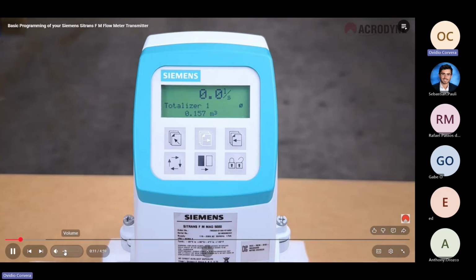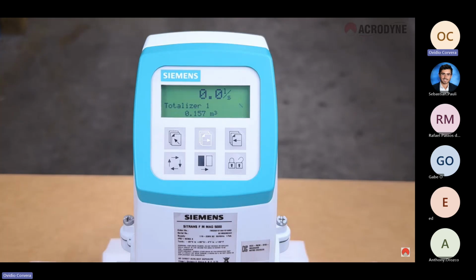To configure the Siemens flow meter transmitter to meet your specific needs, you will need to access the programming mode of the transmitter to make the required changes. To do so, you will first need to understand the input keys and what each of these does. The 6 keys are: the top-up key, used to move up and down through the menu levels as you drill up and down. The forward key, used to move forward through the menu options. The back key, used to move back through the menu options. The change value key, used to cycle through settings, values, and numbers. The select key, used to move the underline icon to the required input field to be changed. And the lock-unlock key, used to get into subheadings and save any changes in settings.